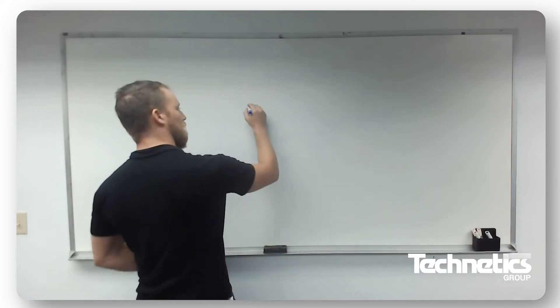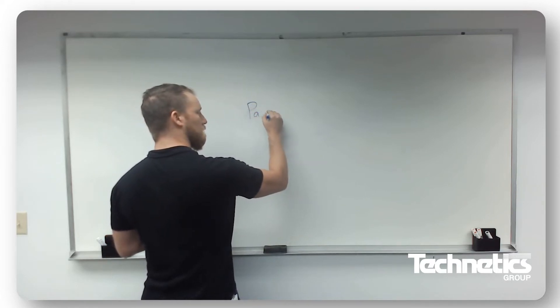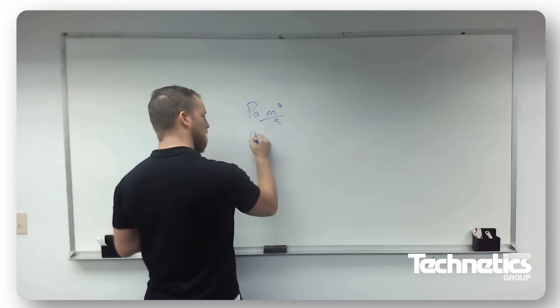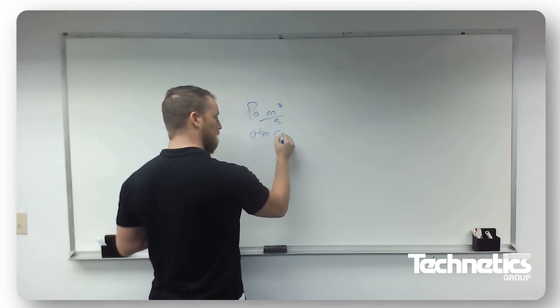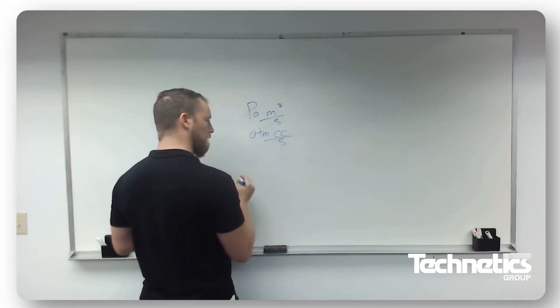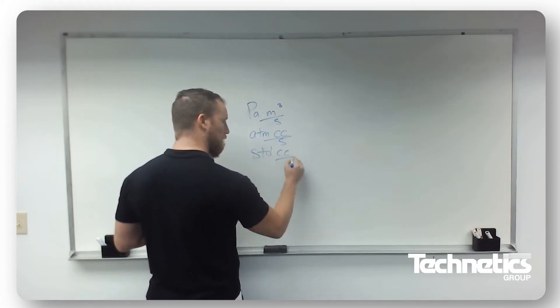Now, understanding leak rates, we need to start with talking about the units, because they're not exactly straightforward. So some of the common units that we see are the Pascal meter cubed per second. Another very common unit is atmosphere cubic centimeter or cc per second. And then we also have standard cc per second.